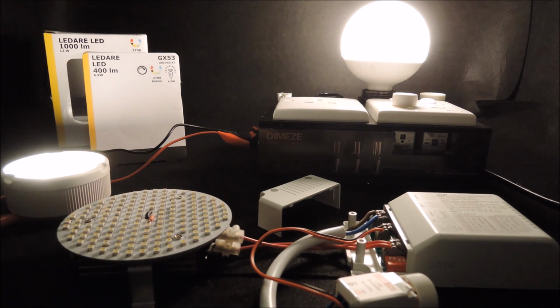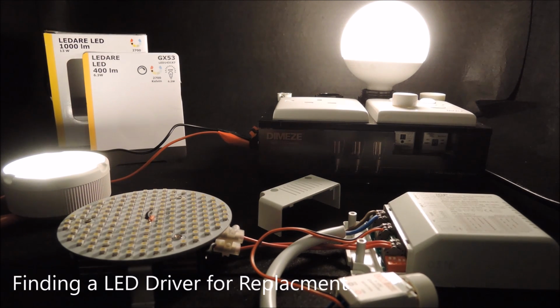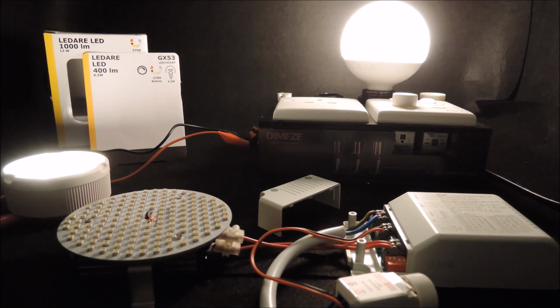As most LED drivers are constant current drivers, the best performance can only be achieved by having the replacement driver with the same set of output rating. However, in reality, sometimes it's not that straightforward to find an LED driver that has the same combination of output voltage and output current for replacement.